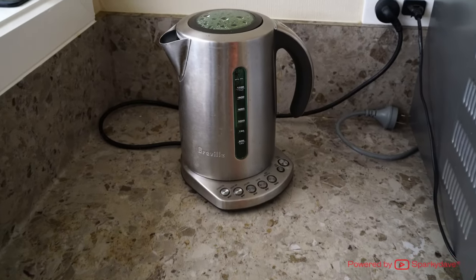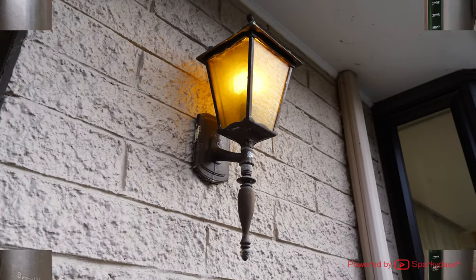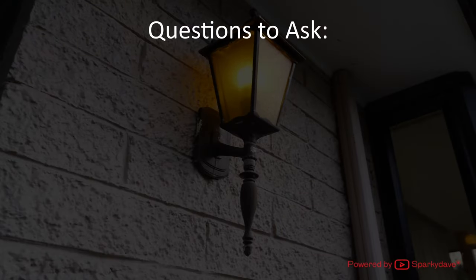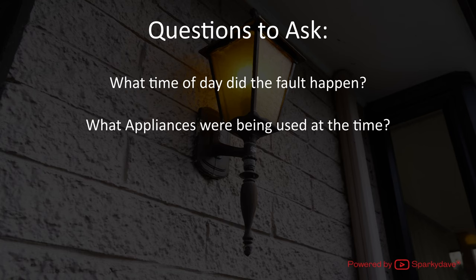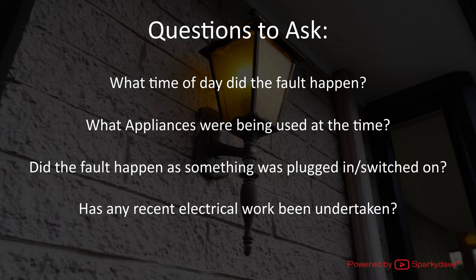The first point of clearing an unidentified RCD fault is to focus on appliances and outdoor lighting. Obtain a brief history from the customer — include what time of day the fault happened, which appliances were being used at the time, if they realized it occurred when they plugged something in, or if any electrical work had recently been undertaken, as these questions may help narrow down what the fault may be.